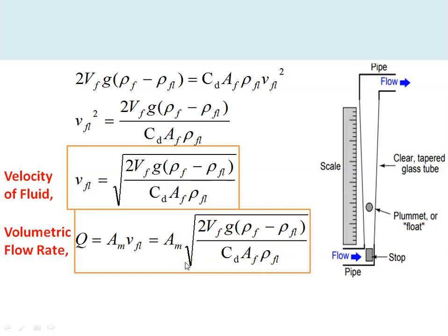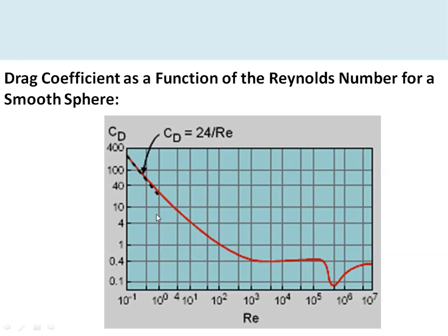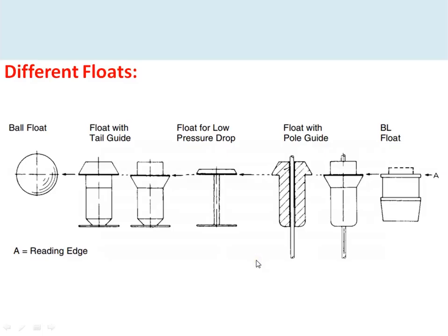The drag coefficient C_D for a smooth sphere (the ball float) varies with Reynolds number. For laminar flows, C_D is not constant and changes with Reynolds number, so rotameters are generally not preferred for laminar flow. Above a certain Reynolds number, C_D becomes approximately constant. Rotameters are generally used for flow rates with Reynolds number greater than 1000, where C_D is essentially constant. Different float types include ball floats, tail-guide floats, low-pressure-drop floats for applications where high pressure drop is unacceptable, and floats with guides used in metal tube rotameters.